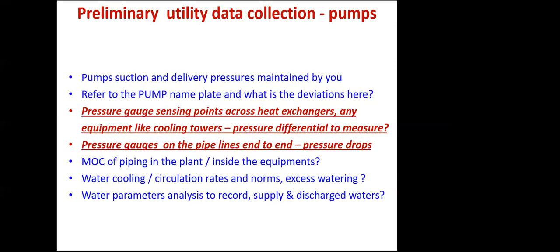What is the suction NPSH, the net positive suction head, to be maintained at the suction of the pump? And what is the delivery pressure in meters? You may buy a pump for 8 meters head delivery, but you will be operating the pump at less than a kg, around 0.5 kg only. Almost 1 kg takes almost 10 meters. It means what you need is the head you need for the delivery and what you are maintaining. All these inputs are important.